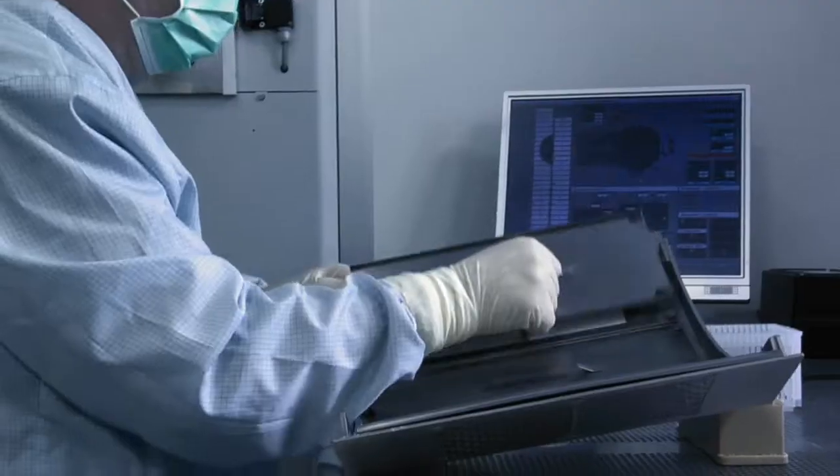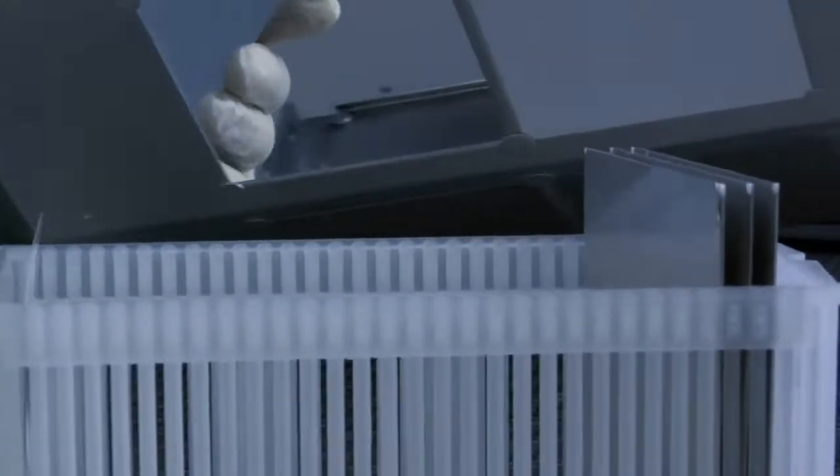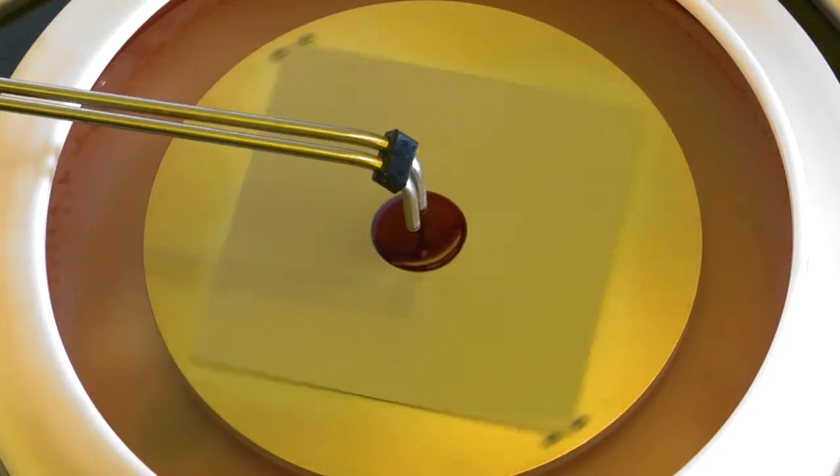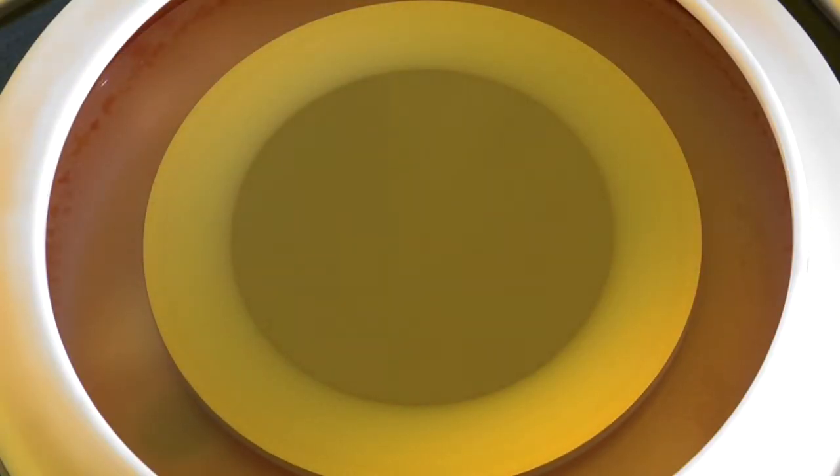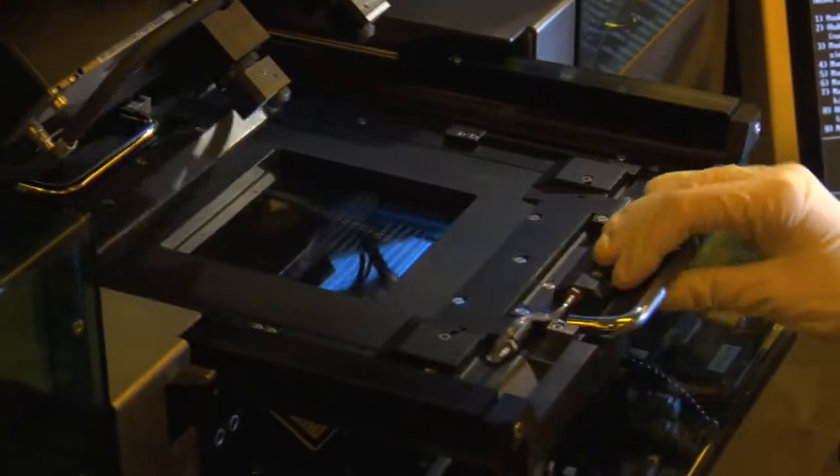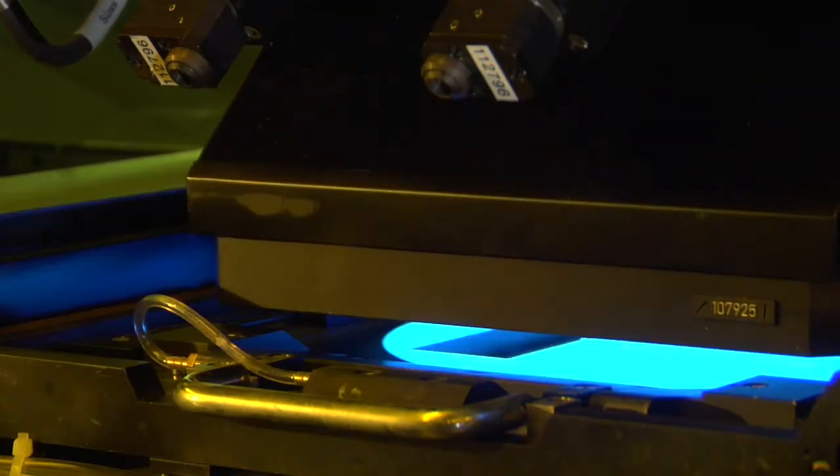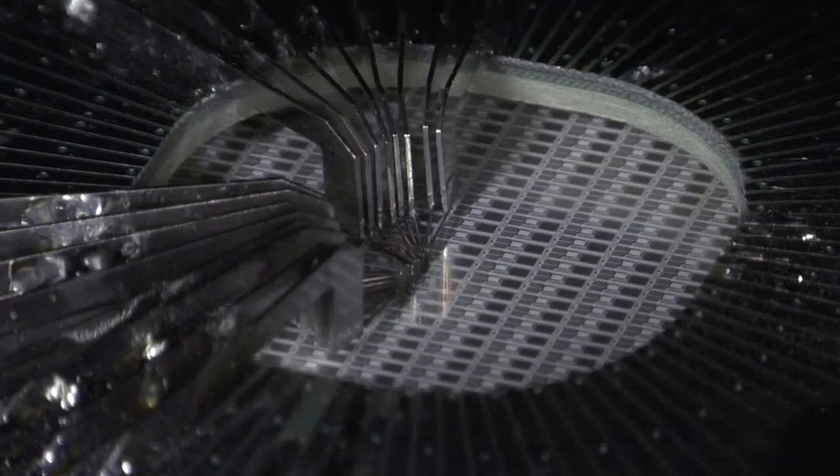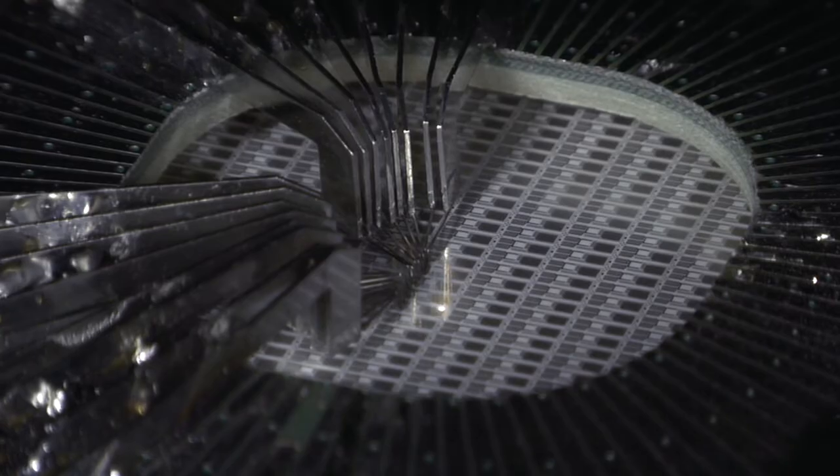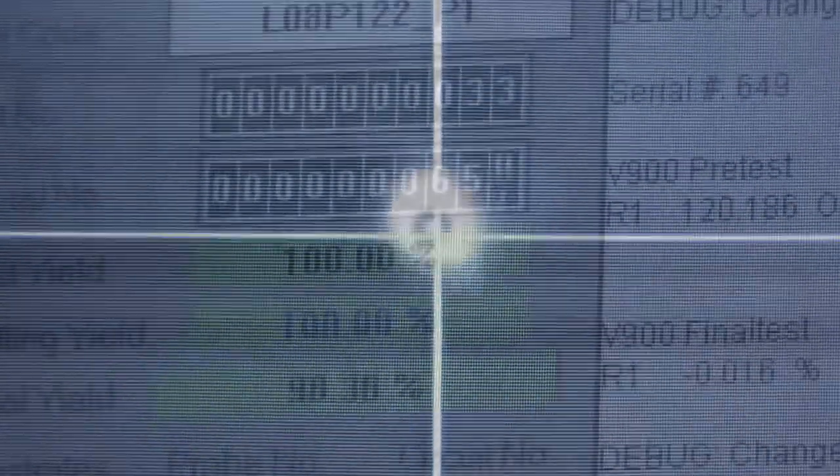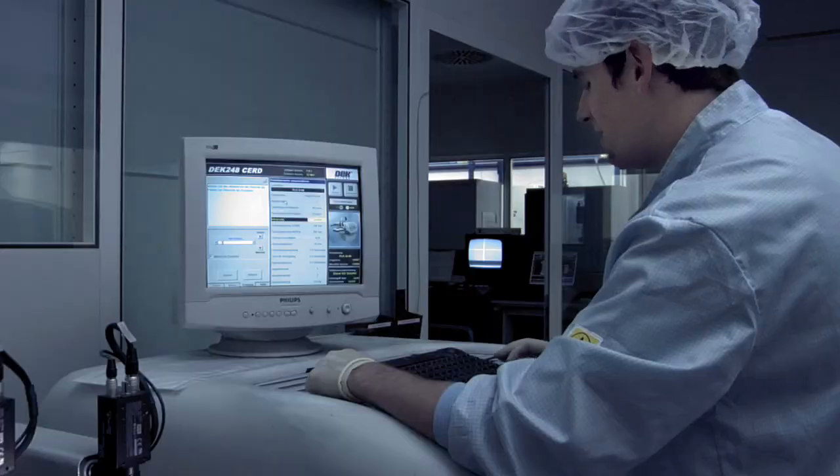Numerous small temperature-dependent resistors are produced on the wafers. A highly precise laser trims them to the exact resistance value - in this case, 100 ohms at zero degrees Celsius.